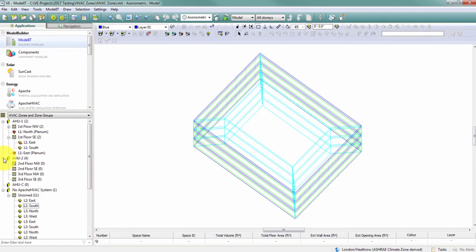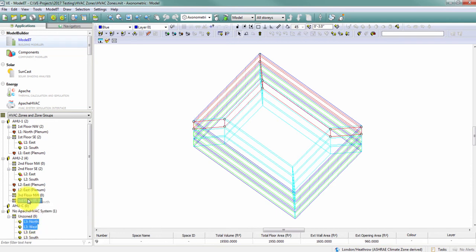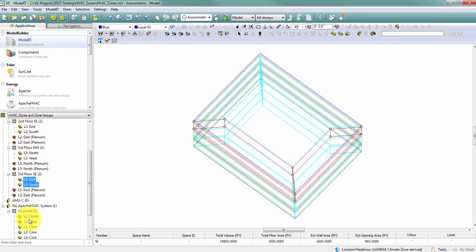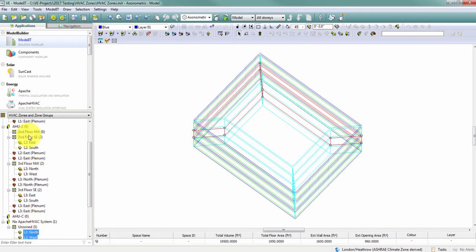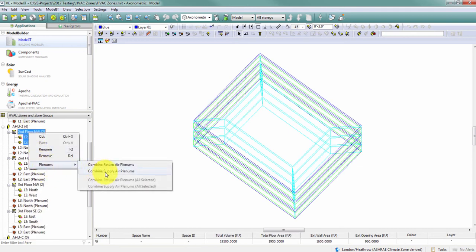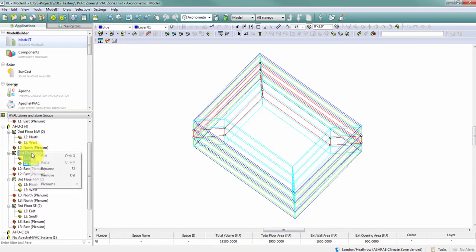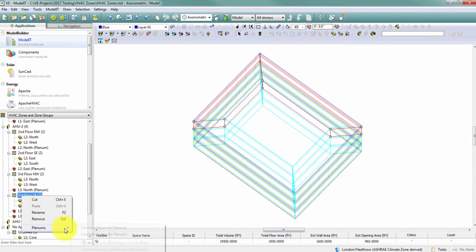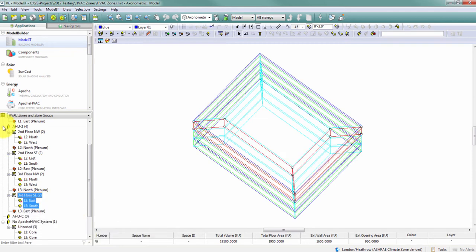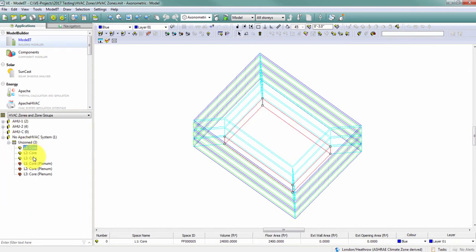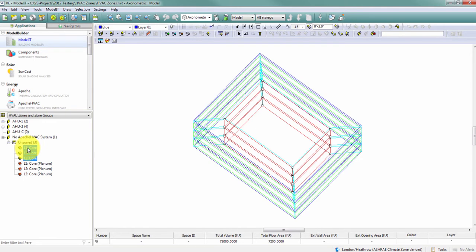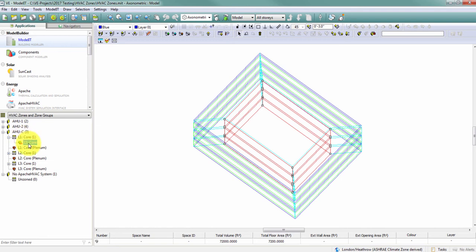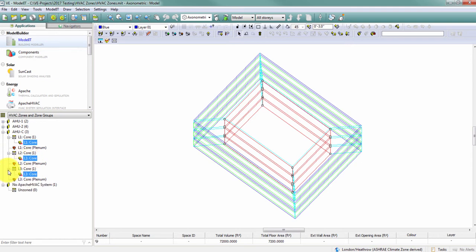Now I can start to drag and drop spaces into these zones. For each of these, I'm going to quickly combine the plenums. My AHU2 zone group is complete with four HVAC zones. In the case of my third air handling unit that serves my core spaces, if I select these three spaces and drag them into AHU-C, the software has created unitary zones for me. So here it's created an L1 core zone that contains the L1 core space, the L2 core zone with the L2 core space, and so on.